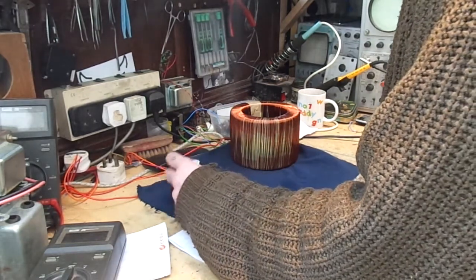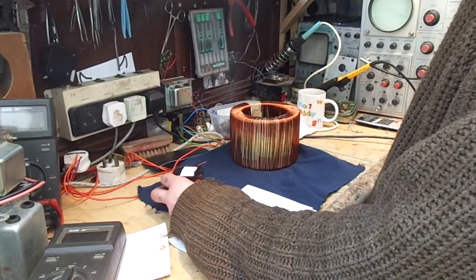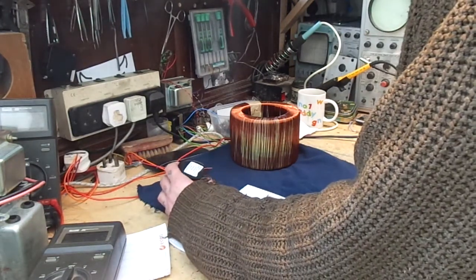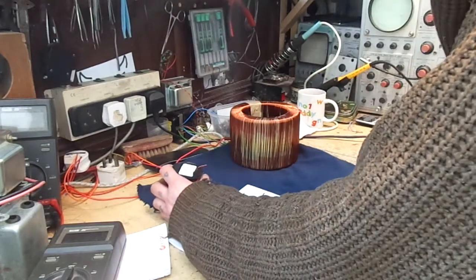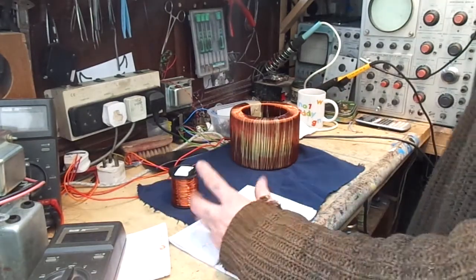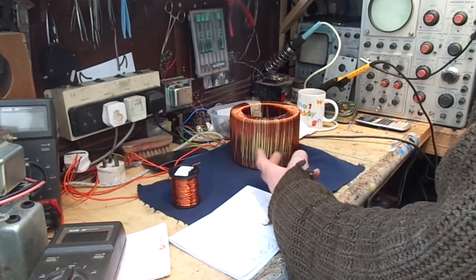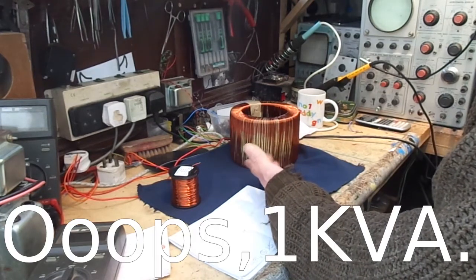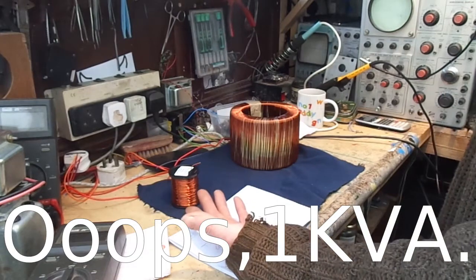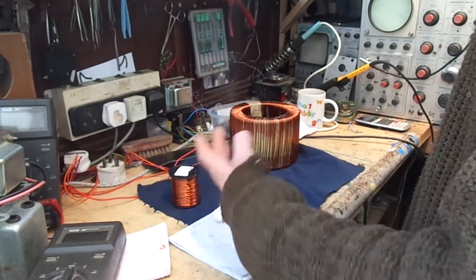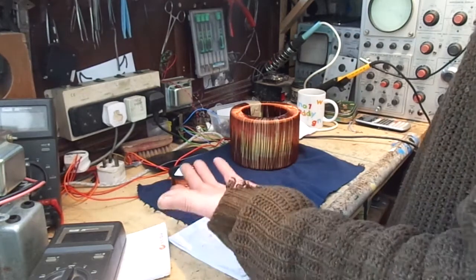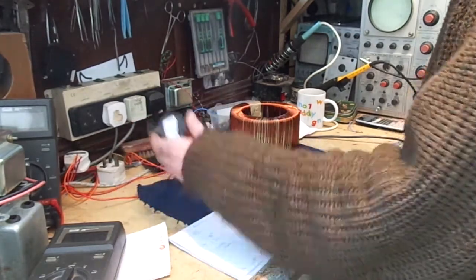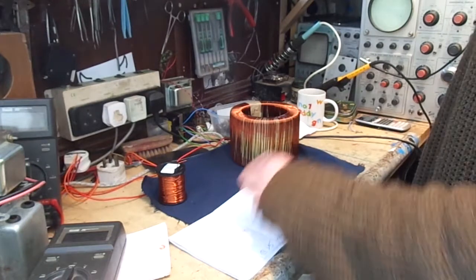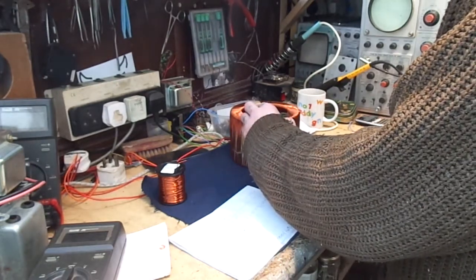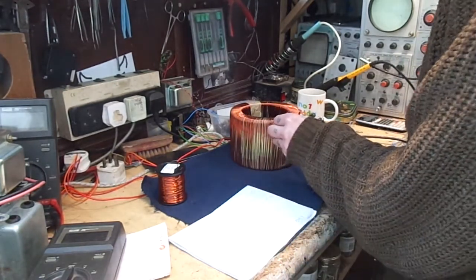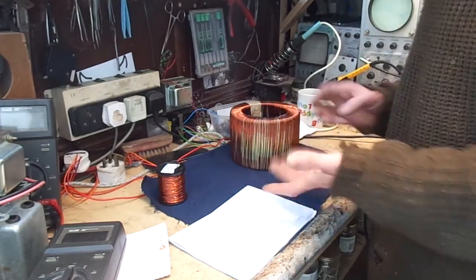This is 18 gauge AWG, American wire gauge, which should be capable in a transformer like this of at least 10 amps. So if we're working on the assumption that this is about a 1 kVA core, then 10 amps is more than sufficient. Our mains voltage here is 240 volts times 10, that's 2.4 kVA, so we're safe there. Because we haven't got any of the information regarding this core's specifications, like I say, we're winging it.